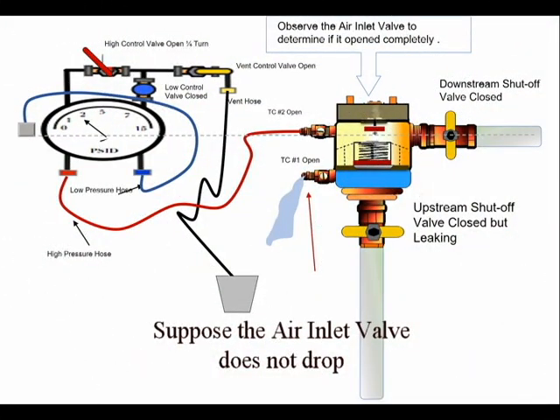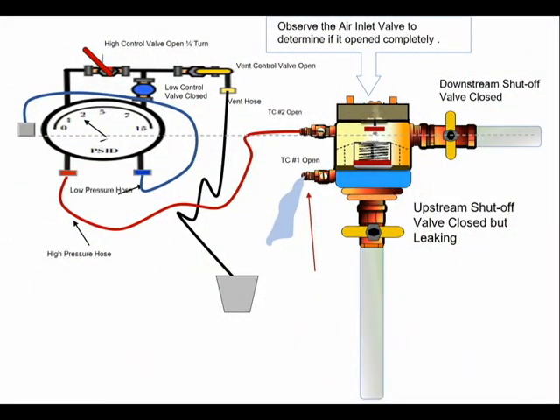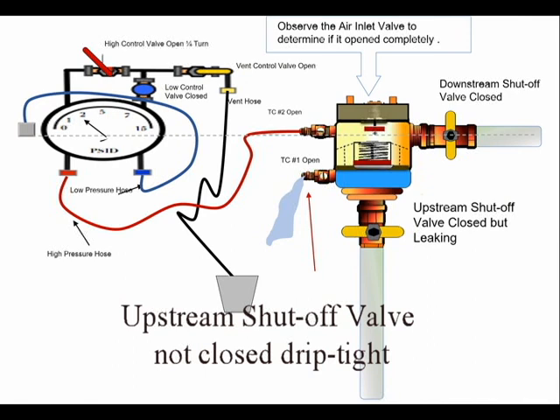Suppose the air inlet valve does not drop. It could be that the air inlet valve is stuck. It also could be that the upstream shutoff valve was not closed, or closed but not drip tight.